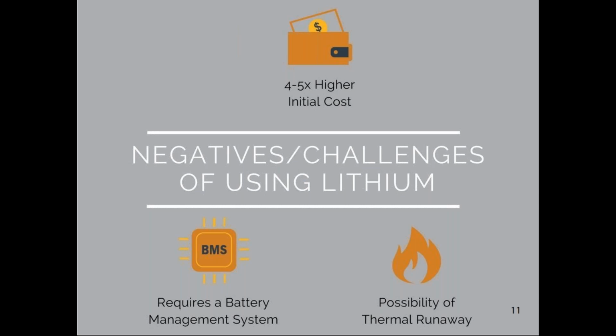Because lithium-ion doesn't derate or degrade nearly as much as lead-acid, as Brendon walked us through, you don't have as much derating based on charge rate, and you don't have as much degrading with age. So you don't need to oversize a lithium-ion pack nearly as much as you would typically oversize a lead-acid pack at the beginning of life, to get the performance and capacity you need at end of life. So you can mitigate this, but there's still a higher cost up front.